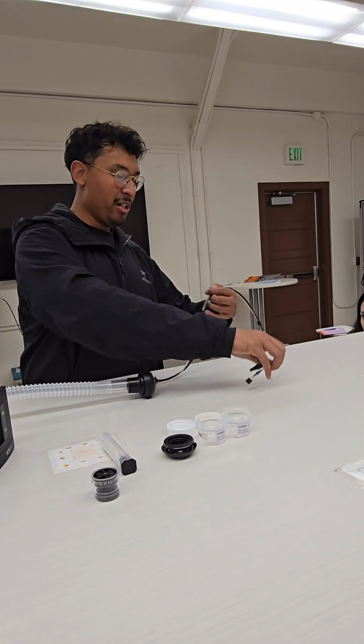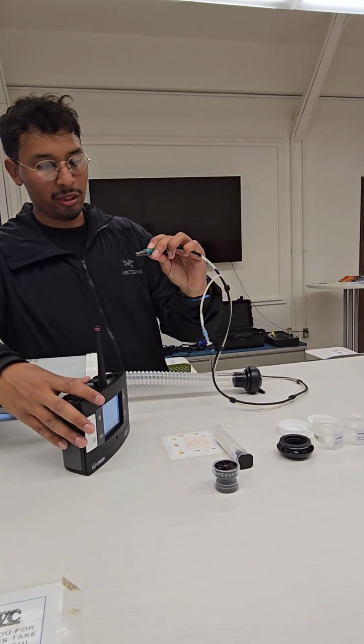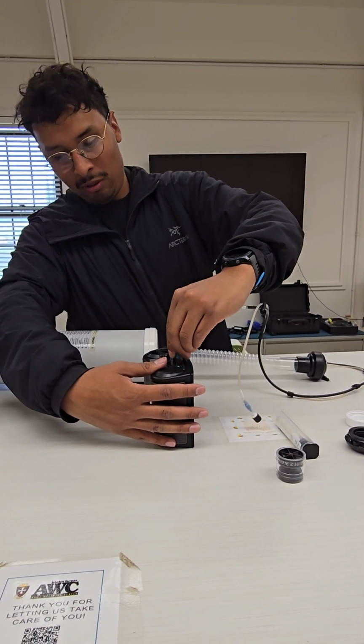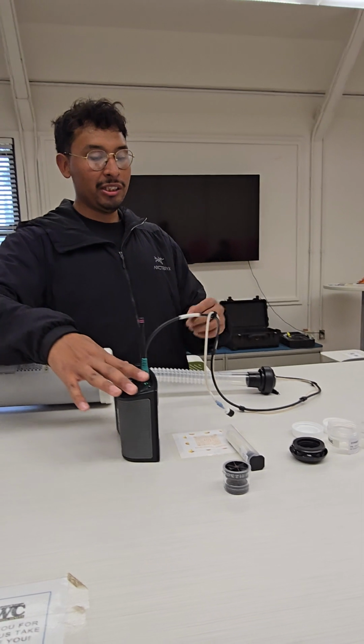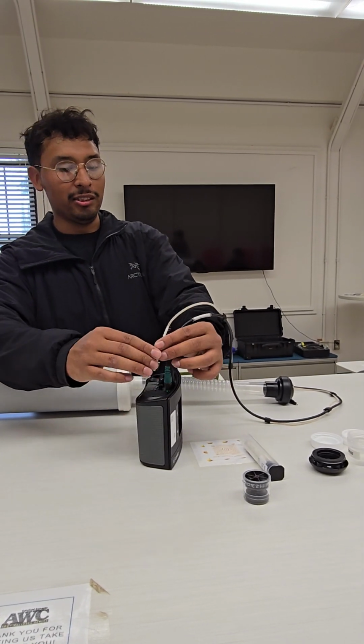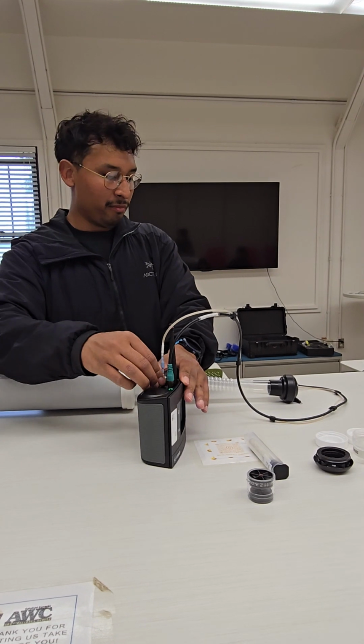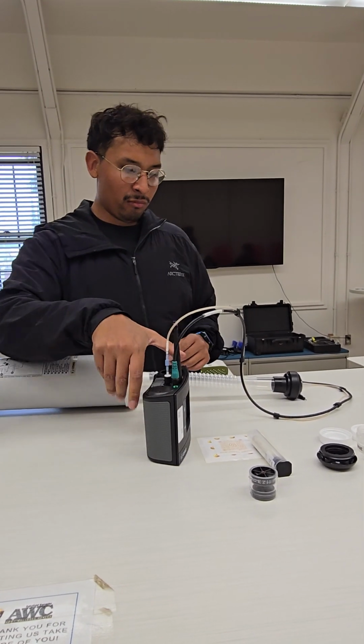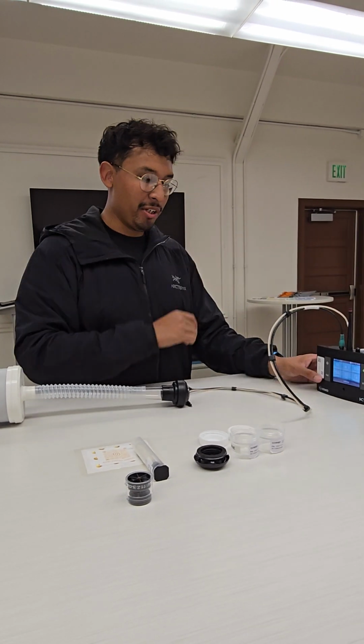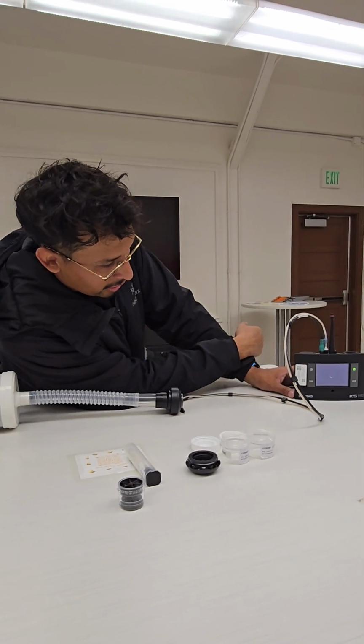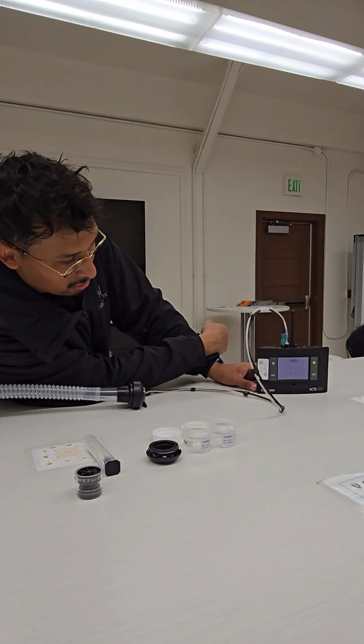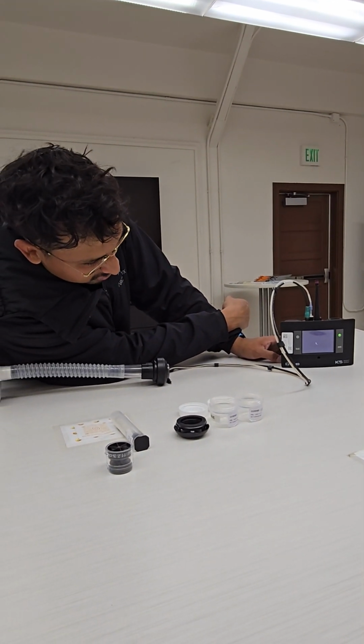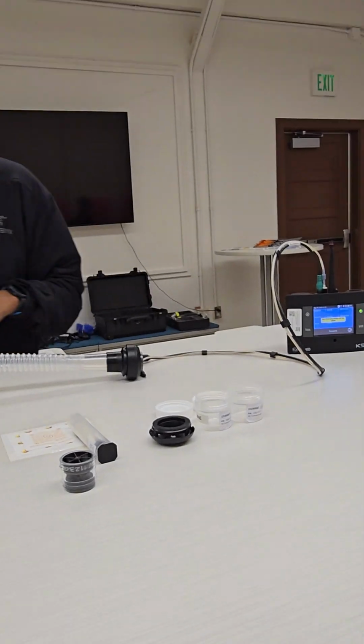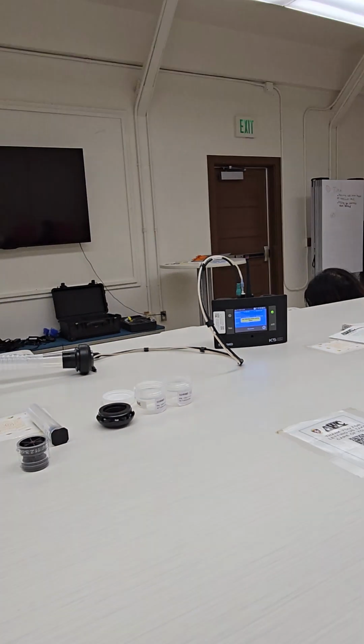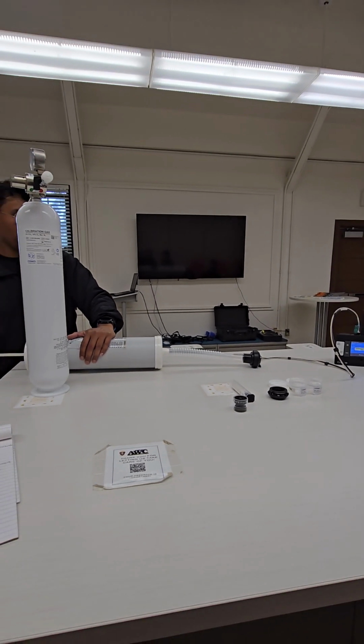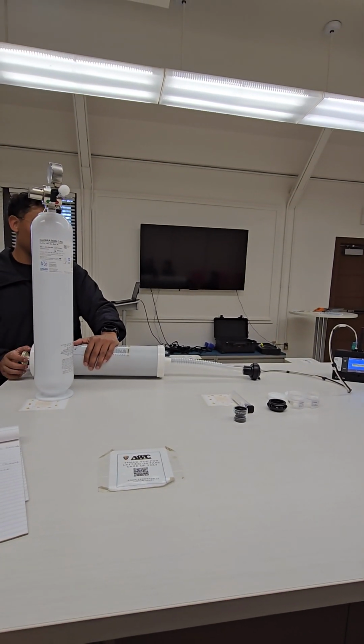So from here, all we need to do is connect the flow meter onto the K5. And you're technically good to do the calibration, but since I know that we'll be doing the reference gas and scrubber, I'm going to go ahead and connect this. And that's pretty much it. From here, you go into flow meter, and then it'll ask you to start performing strokes in a second. So you pull all the way out, push all the way in, and you don't have to go at a certain flow rate.